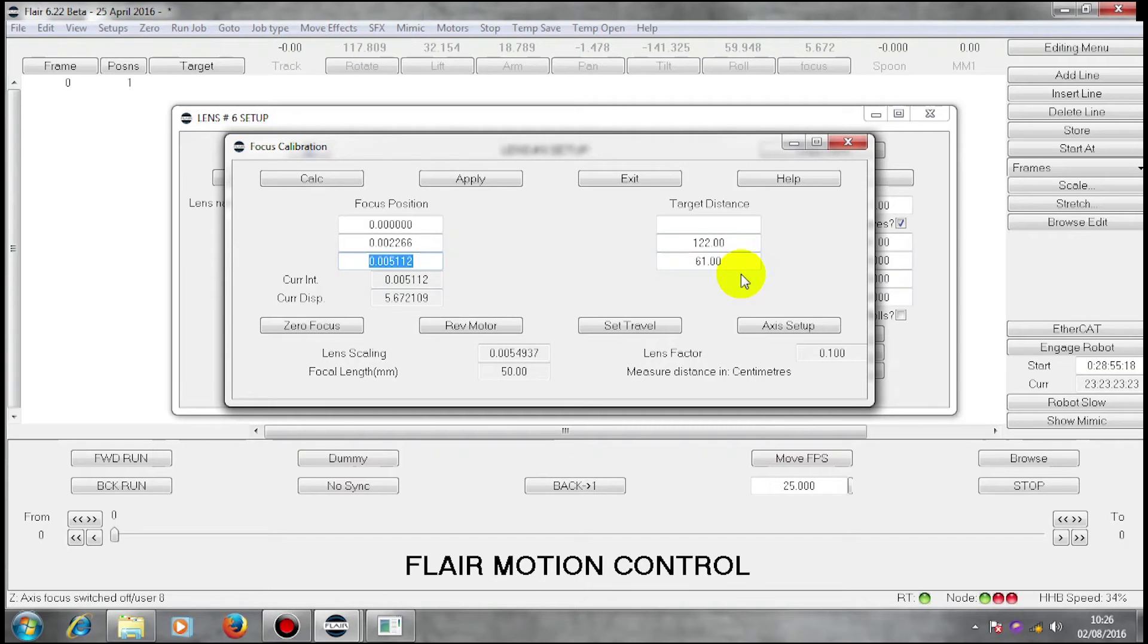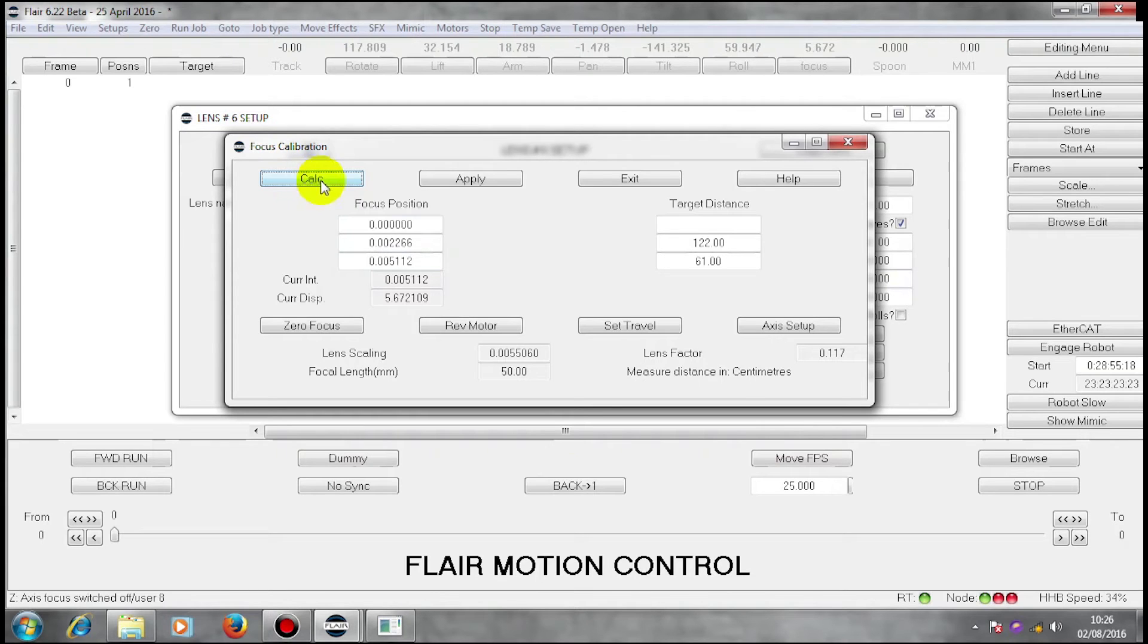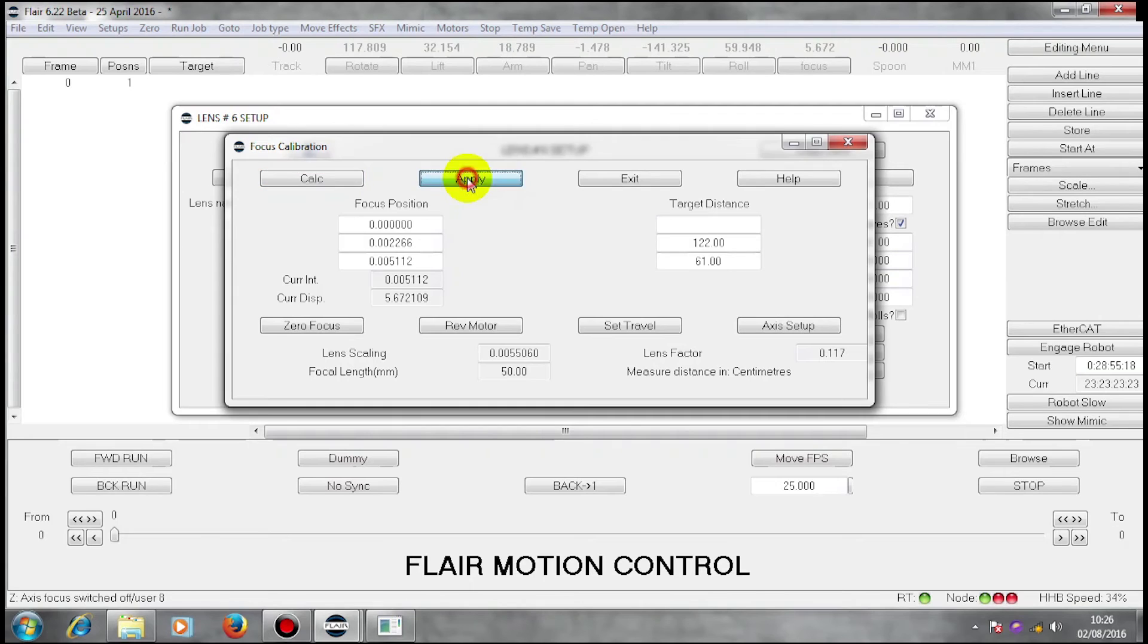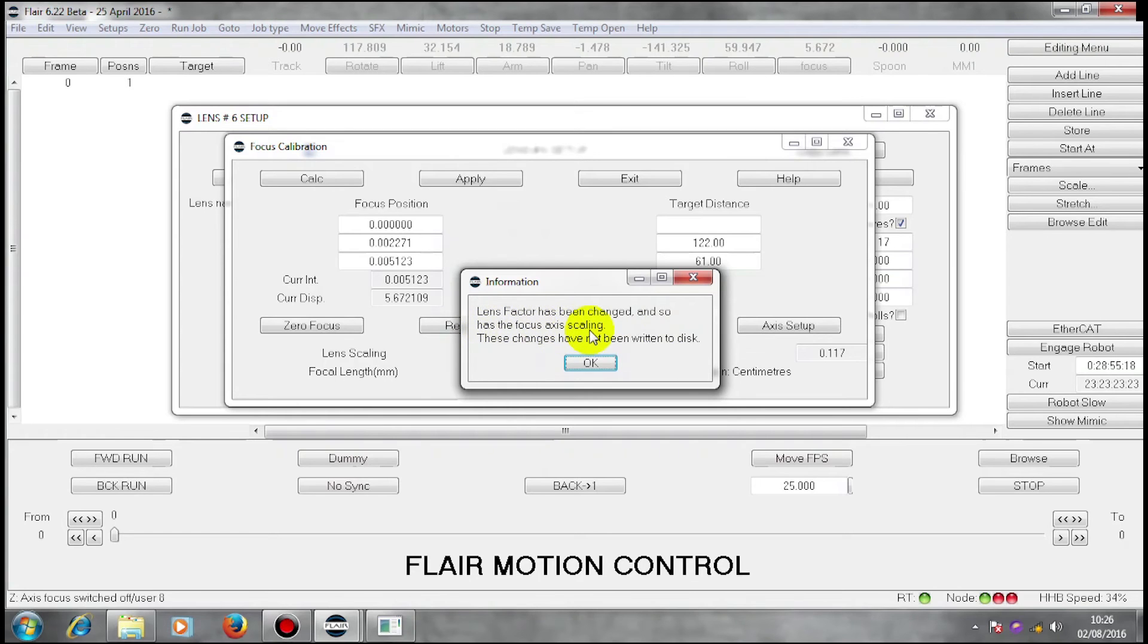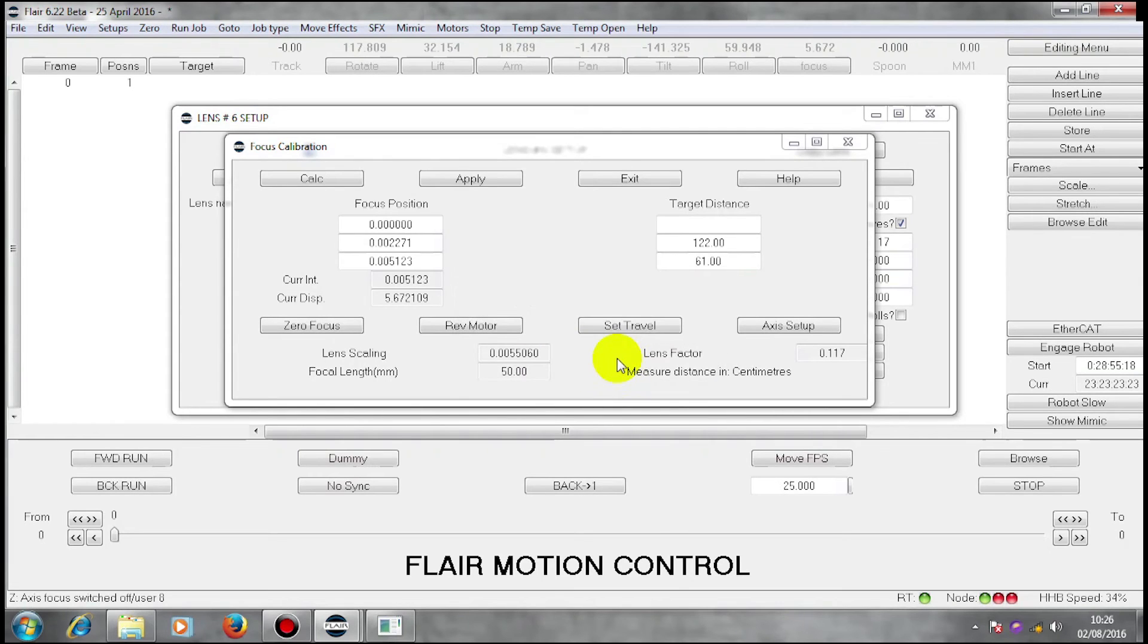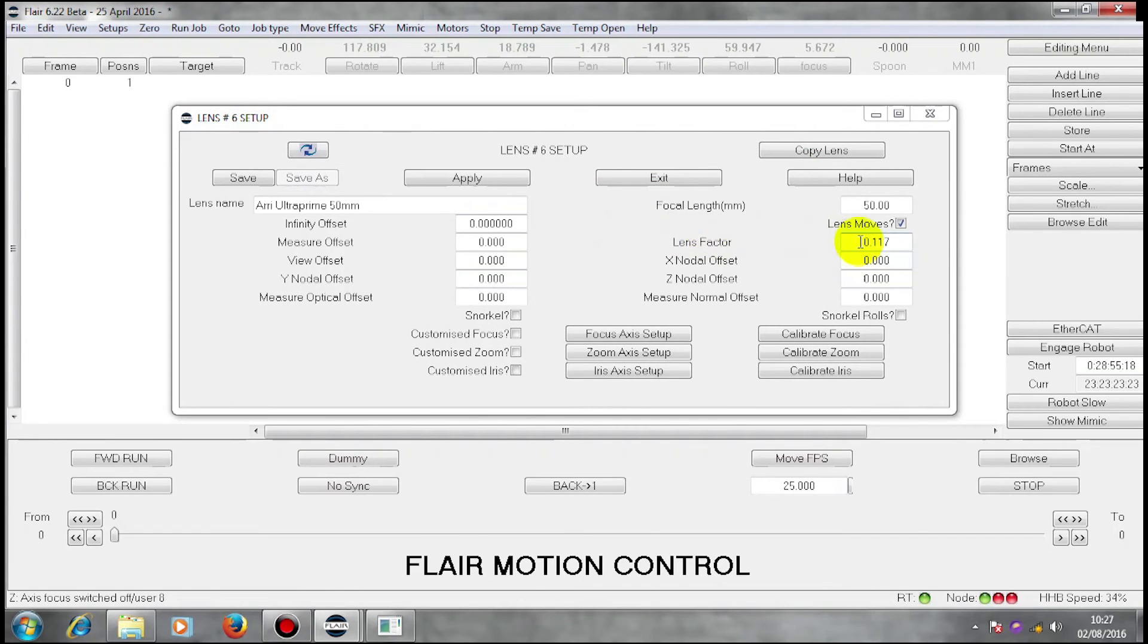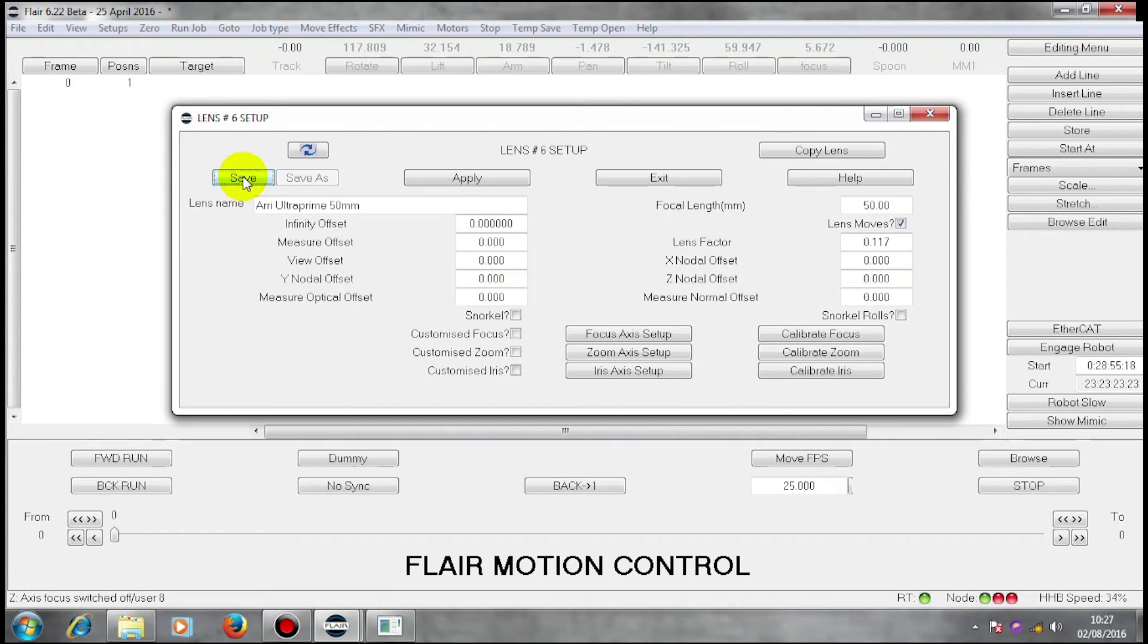This is sufficient to define the curve of this lens. So I'm now going to use calculate and press this once. Now that I've done the calculation, the lens scaling has changed and the lens factor has been calculated for me. I can now apply this data. This uses it in the setups as I am doing. And it says here, lens factor has been changed and so has the focus axis scaling. These changes have not been written to disk. So I can exit from this box. There is my lens factor. Because that has not been written to disk, I'm going to write it to disk by clicking on save. And I'm going to use it today by clicking on apply.